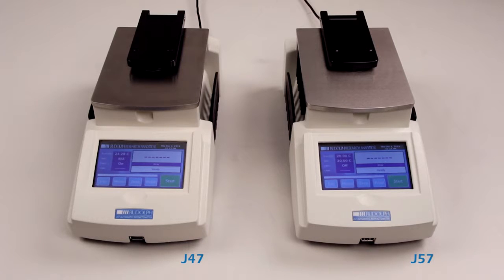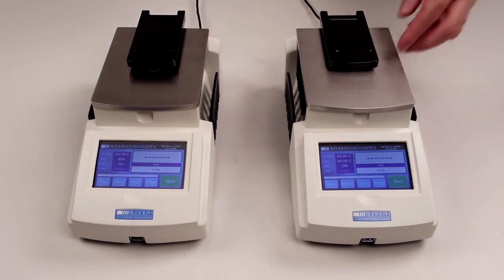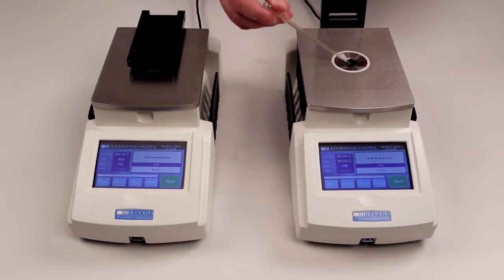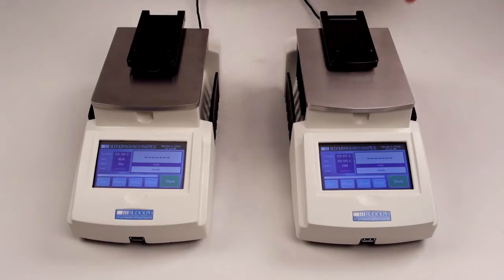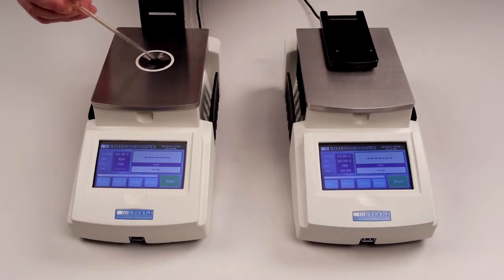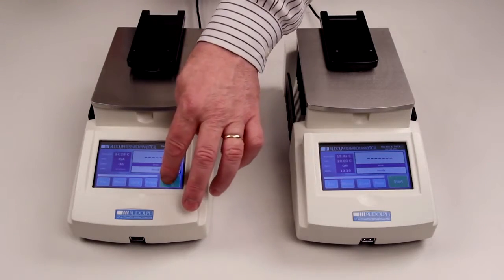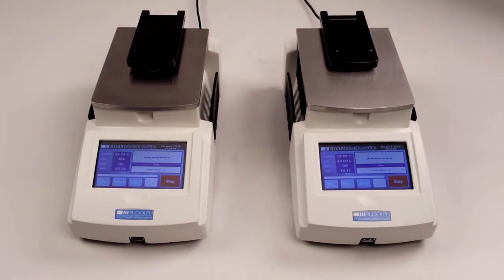These instruments have both been on for a while, and what you'll notice is sitting in a room at ambient temperature, the J47 instrument will read approximately 22 to 23 degrees Celsius. The J57, being temperature-controlled, will hold steady at exactly 20 degrees C. Why does it matter in a real-world situation? If you're working in a factory environment where most of your samples are primarily sugar and water, temperature correction will work quite well. As an example, we will measure something simple like sweet iced tea. You'll see it will read about the same on both instruments.